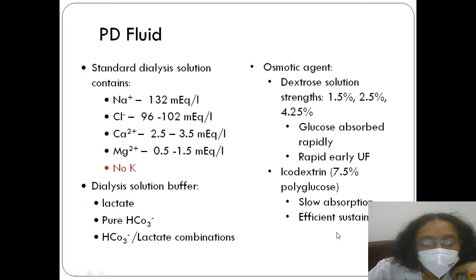Now, in the peritoneum you cannot apply a transcapillary pressure, so you need an osmotic agent to draw the fluid. The dialysate fluid should have a higher concentration gradient than the patient's plasma to pull out fluid. And this osmotic gradient is created by putting in dextrose. Different strengths are available: 1.5, 2.5 and 4.25. Sometimes when these don't work, you can use something called icodextrin, which is a polyglucose that is slowly absorbed from the circulation, so it stays in the abdomen for a longer time, creating the concentration gradient and facilitating the ultrafiltration.